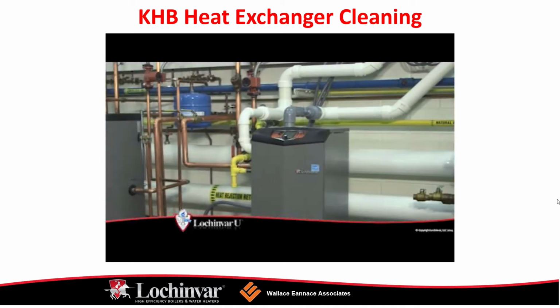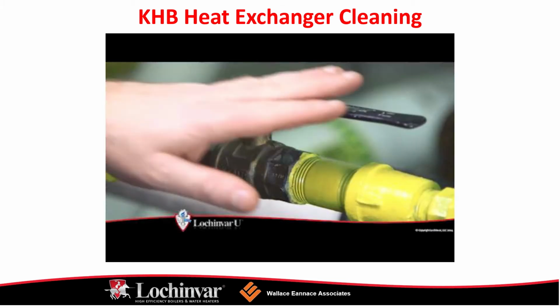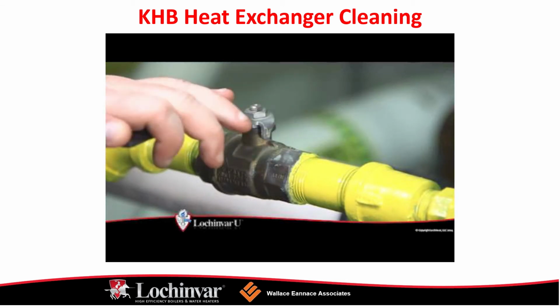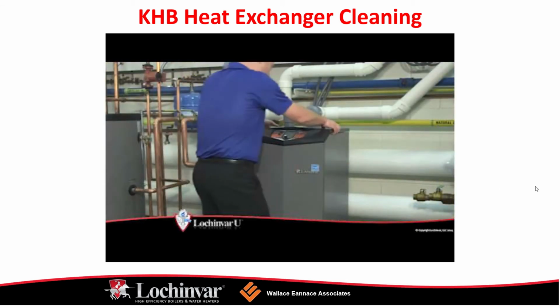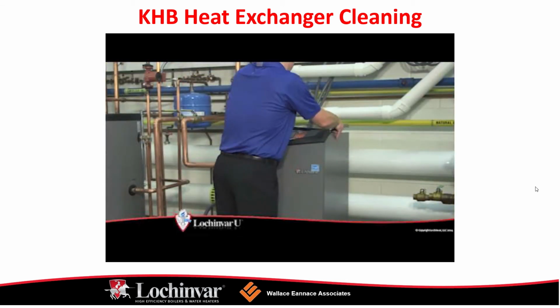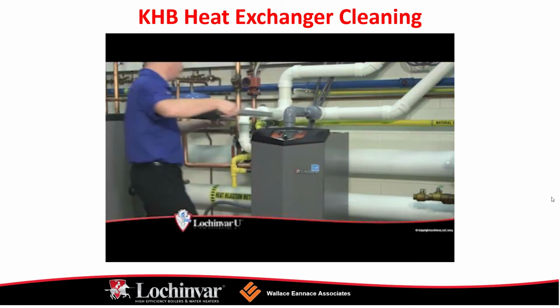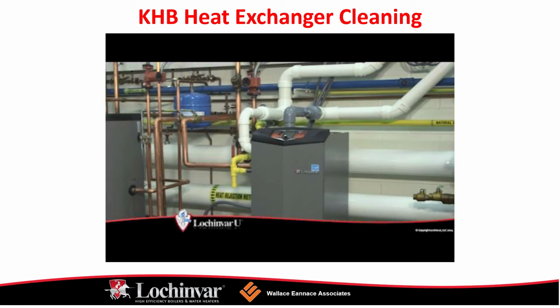So speaking of cleaning the heat exchanger, again, it's going to be if combustion or performance indicate the need for it, we will then clean it. We will also remove and clean the burner using compressed air only.